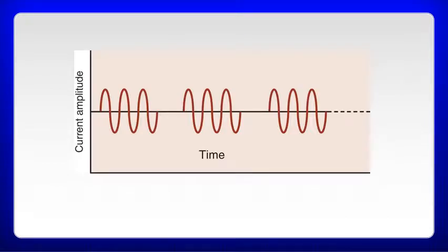So here we look at a concept, what you would call a time modulated alternating current. This is again showing you the difference between an extrinsic versus an intrinsic duty cycle. This is showing you the intrinsic duty cycle, where you get little bursts that are created. Each burst has a carrier frequency basically determined by the machine. Sometimes machines do let you select a different carrier frequency, and we'll talk about how to deal with that and what that means for your treatment.